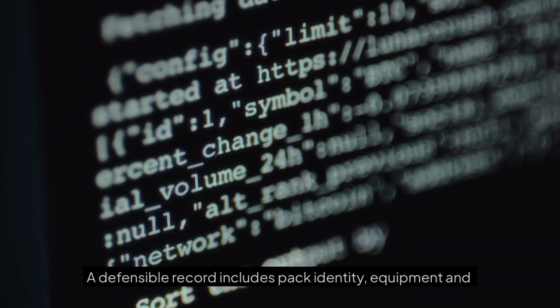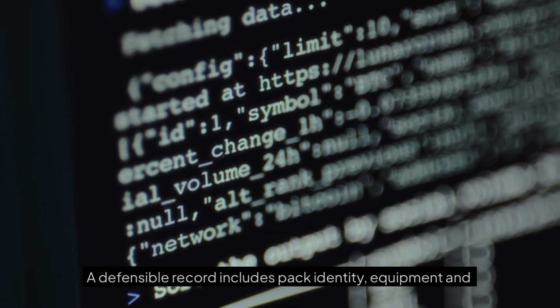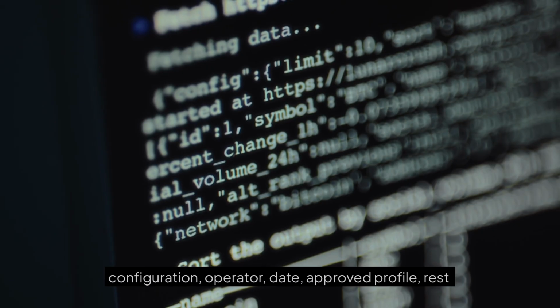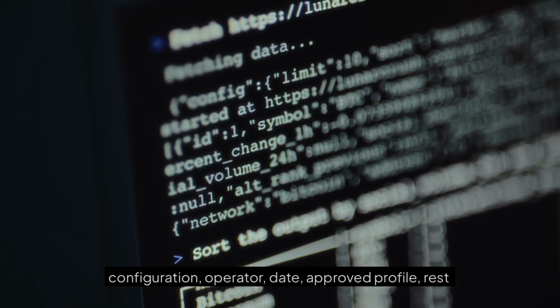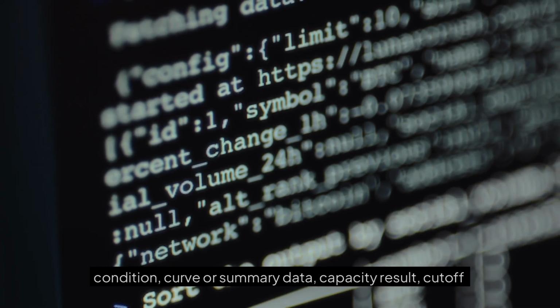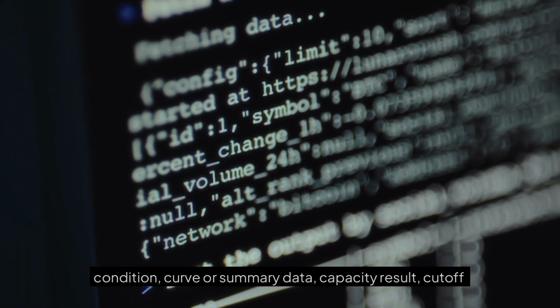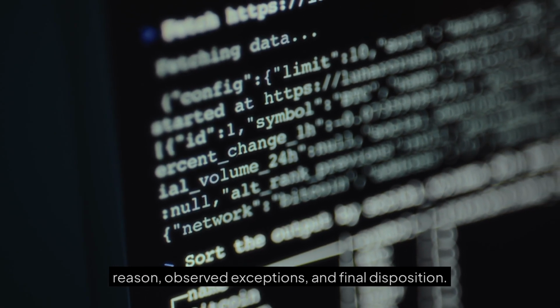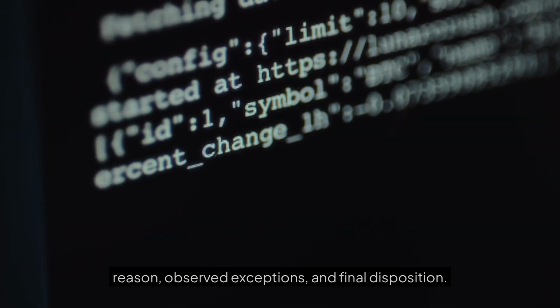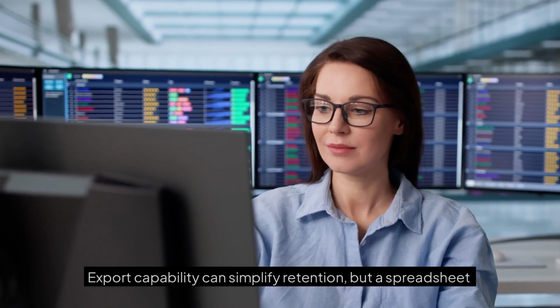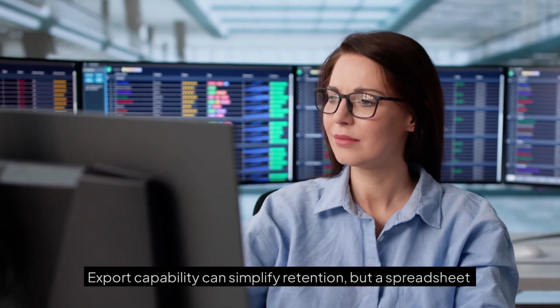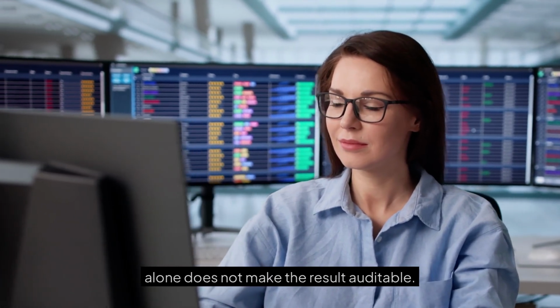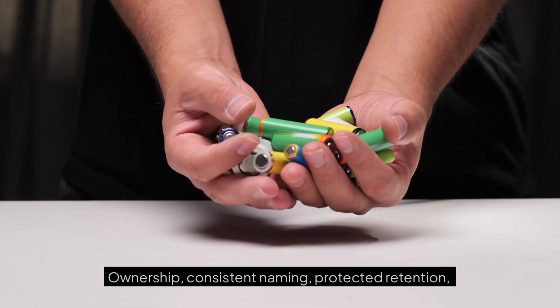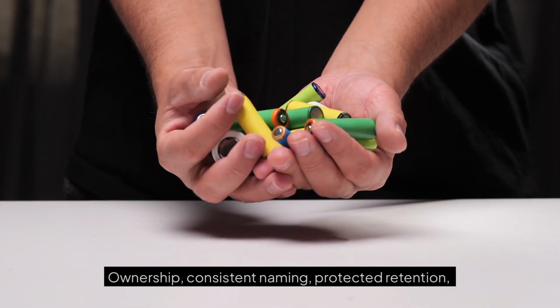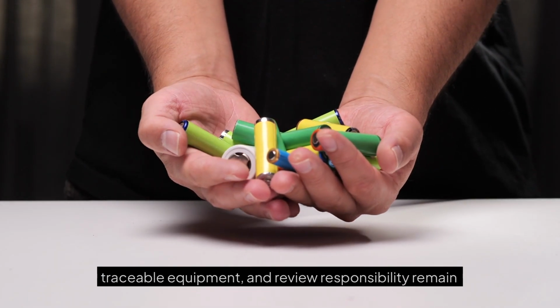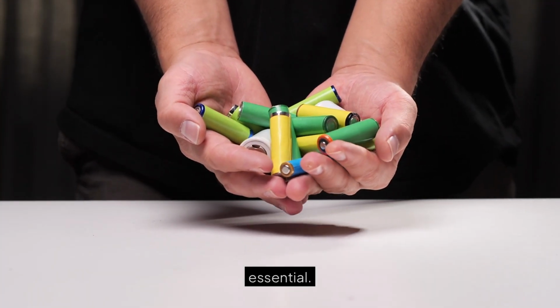A defensible record includes pack identity, equipment and configuration, operator, date, approved profile, rest condition, curve or summary data, capacity result, cutoff reason, observed exceptions, and final disposition. Export capability can simplify retention, but a spreadsheet alone does not make the result auditable. Ownership, consistent naming, protected retention, traceable equipment, and review responsibility remain essential.